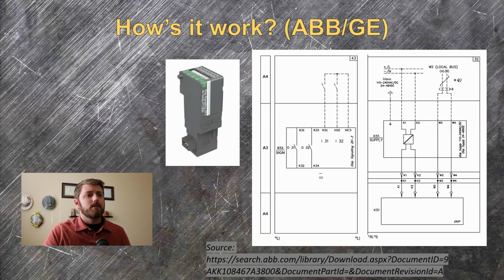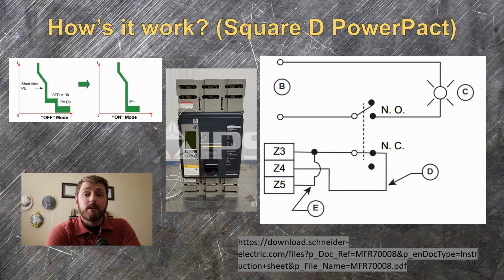For ABB trip units, RELT mode only works if the breaker is provided with a digital input module, like the signaling 2K module shown here. But it works effectively the same, except that the power supply is another expensive proprietary thing you got to physically plug into that breaker. Square D does it in two different ways. For their molded case PowerPact breakers, a maintenance mode switch sends a direct 24 volt signal to the trip unit and reduces the trip time using the same inputs that you'd use on the ZSI system. I'll make a video about ZSI at some point, I'm sure.